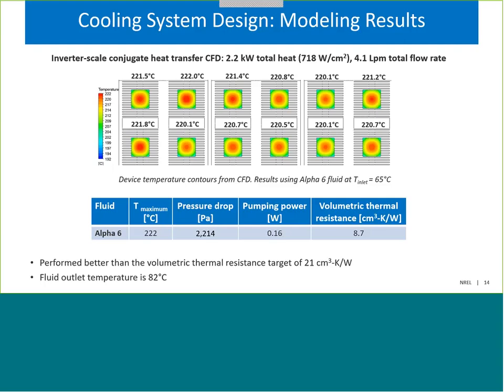In this case, we imposed 2.2 kilowatts of heat that was evenly distributed through 12 devices. That resulted in a device heat flux of about 718 watts per centimeter squared. We used alpha 6 fluid at a total flow rate of 4.1 liters per minute and an inlet temperature of 65 degrees C. Essentially the fluid comes in from the top right-hand side. It impinges on the fins that are directly behind the devices. And the results are summarized in the table below.